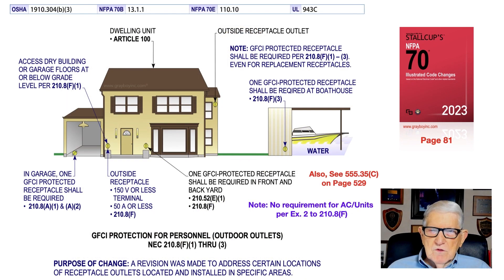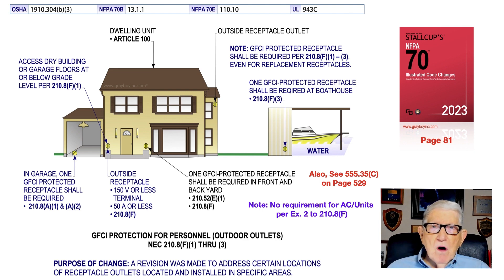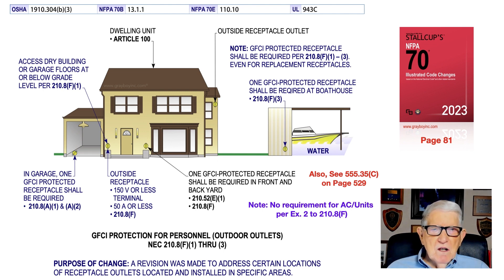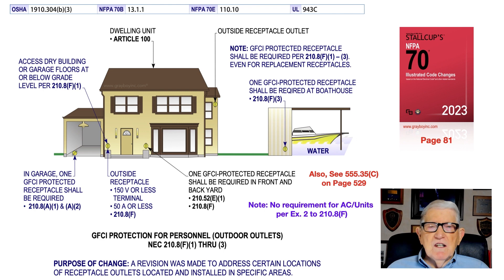This illustration deals with GFCI protection for personnel for outdoor outlets. This gives you a general overview of specific locations where GFCI protection is required — such as inside the garage, crawl spaces, unfinished basements, and similar areas. This particular illustration deals with outside receptacles, including a receptacle on a boat dock near water. You can read more about this in 555.35C on page 529 of the NEC.